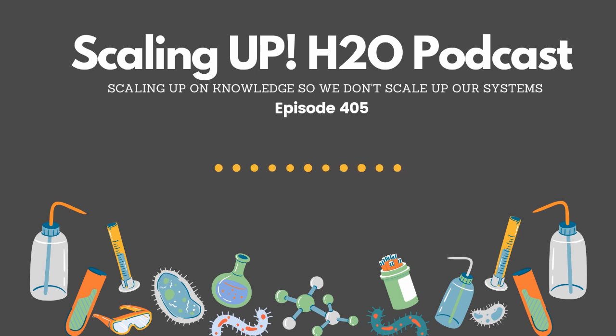Part of my job, and very frequently, was boiler inspection. As you know, boilers and steam systems in general are critical components in any industrial facility. So at that time, I started to inspect boilers, fire side, water side, looking for any deterioration, corrosion in the water tubes, in the steam drum, mud drums. And so at that moment, I started to be involved in the water treatment.